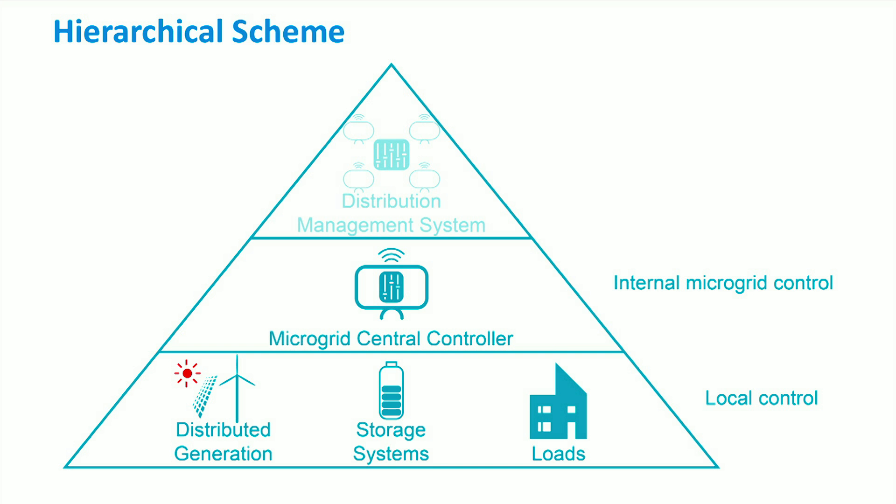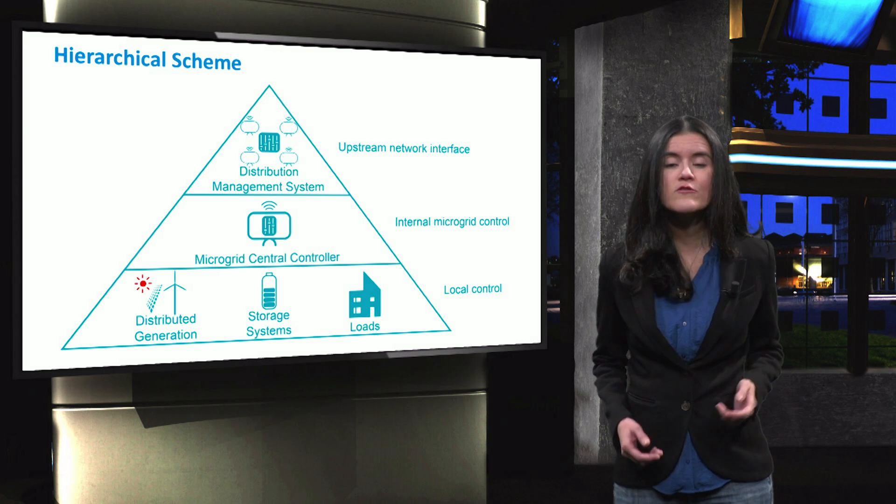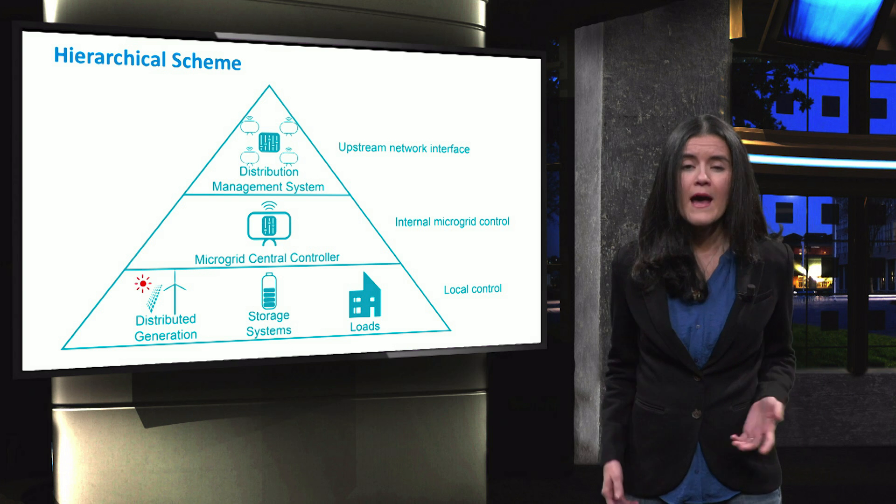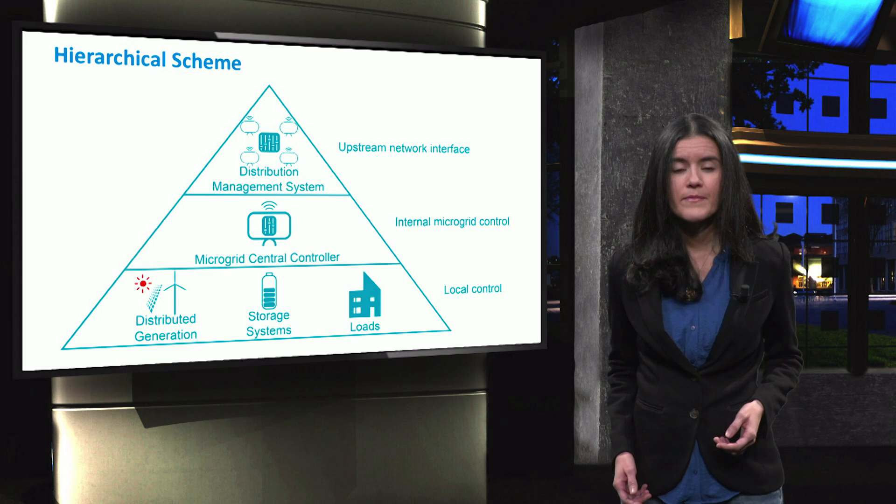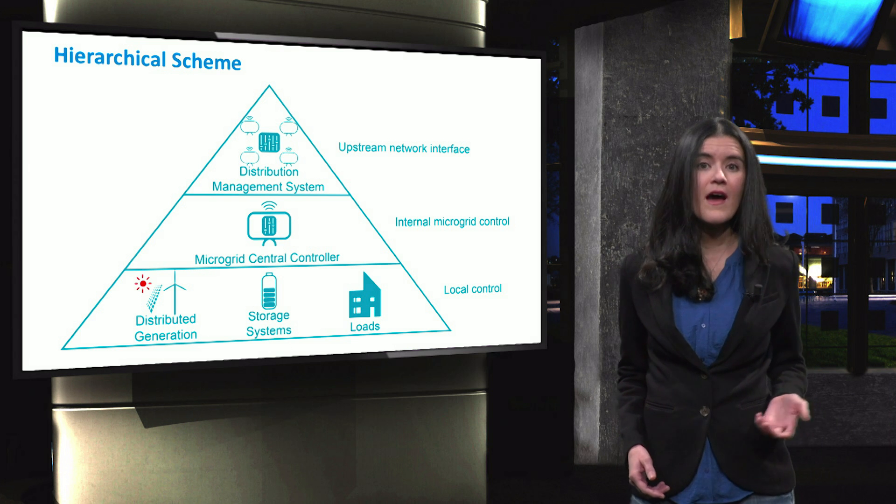At the second level, the microgrid central controller acts over the internal control. Here, the main goal is to adjust the reference points of the distributed generators in the microgrid. Also, the internal control manages synchronization between the microgrid and the external grid. When the microgrid is in grid-connected mode, at the top level, we find the upstream control. The distribution management system is responsible for this control level and it mainly addresses the exchange of power between the microgrid and the external grid, taking into account electricity market and regulatory signals.